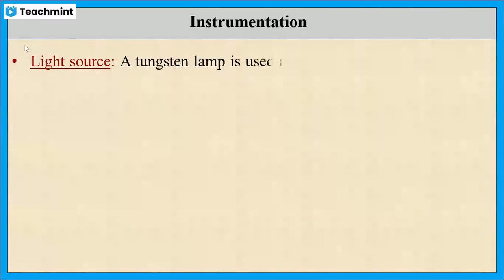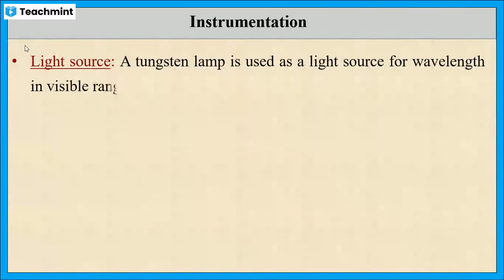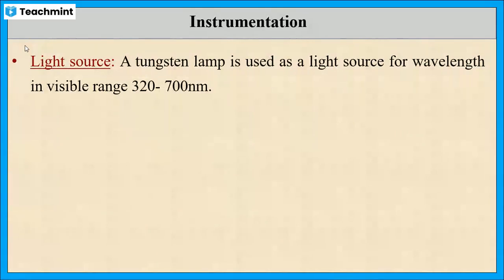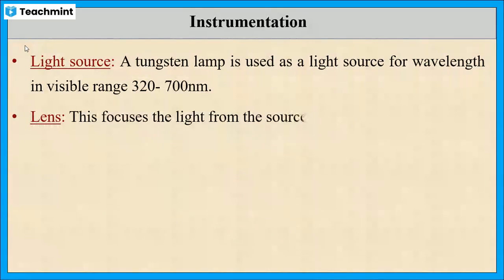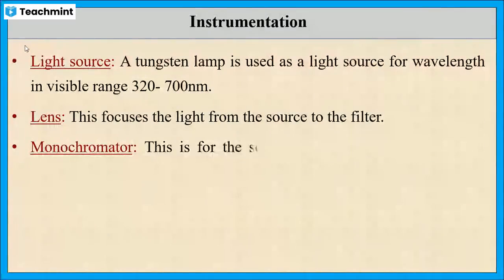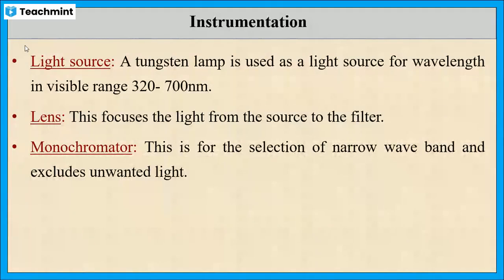Usually, a tungsten lamp is used as the light source, which gives light in the range of 320 to 700 nanometers. The role of the convex lens is to focus the light from the source to the filter. The monochromator, or filter, selects a narrow wave band and blocks the unwanted light.